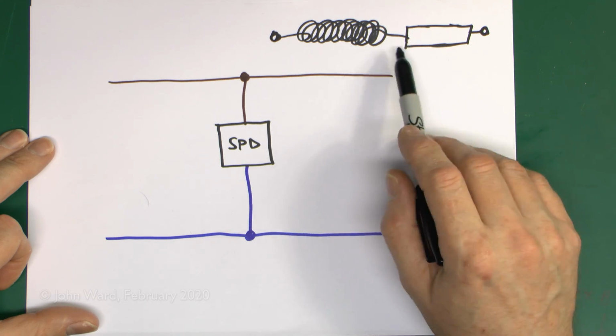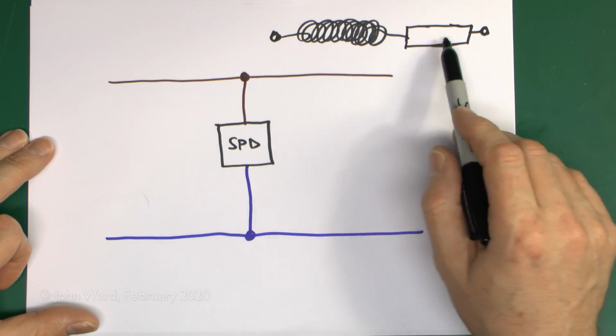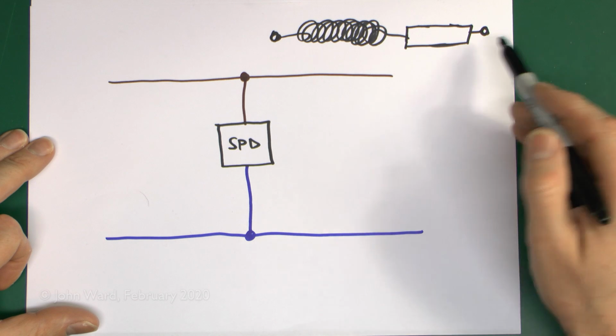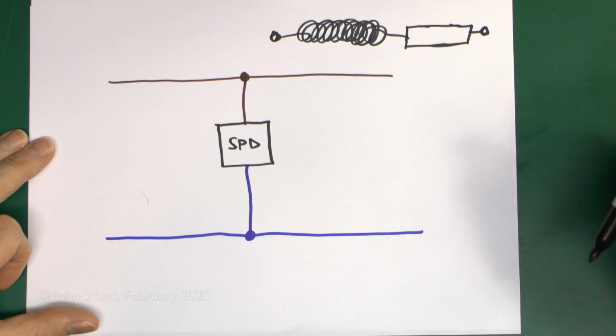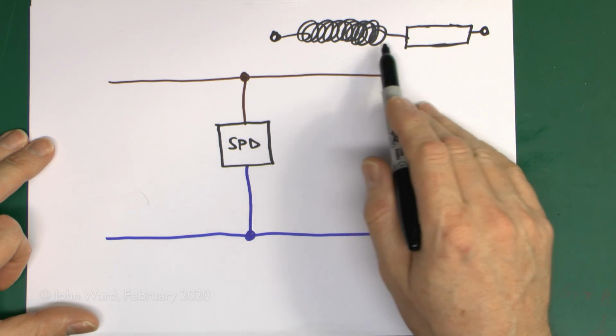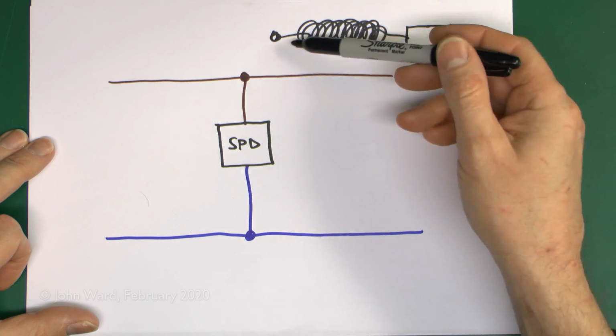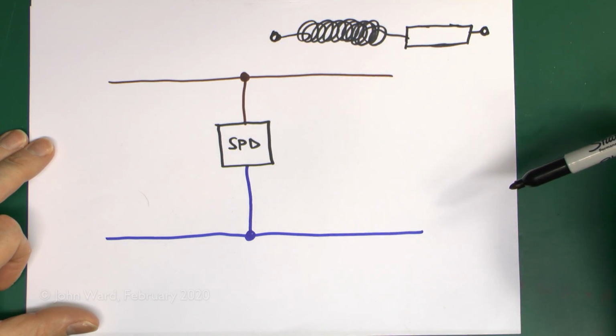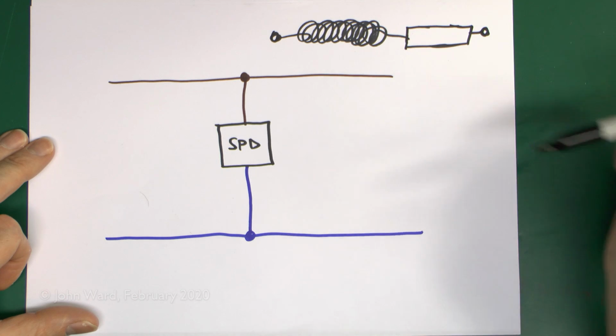And this is important because if you just connect a normal fluorescent tube across the supply and it actually is lit up, there's nothing in it to limit the current, so of course the tube is destroyed. So this just limits the current that goes through there, and it is normally just a big coil of wire wound on some kind of magnetic or metal form.